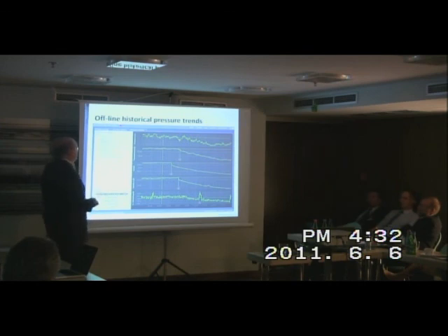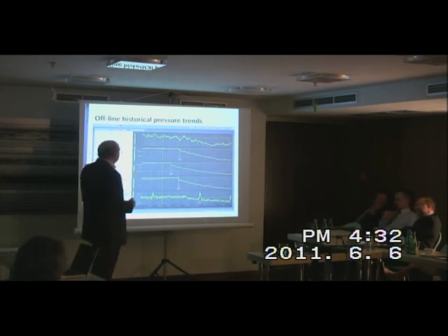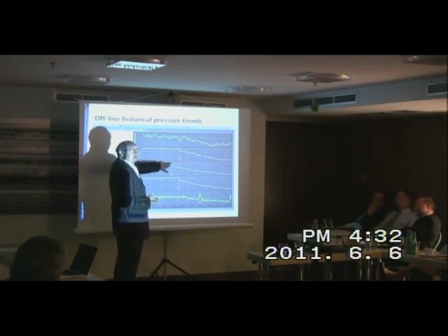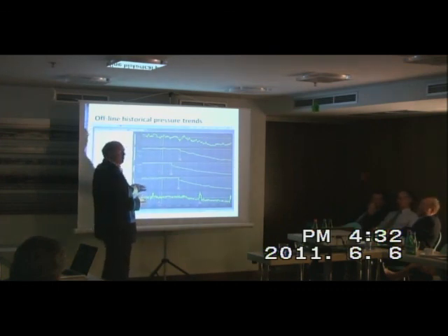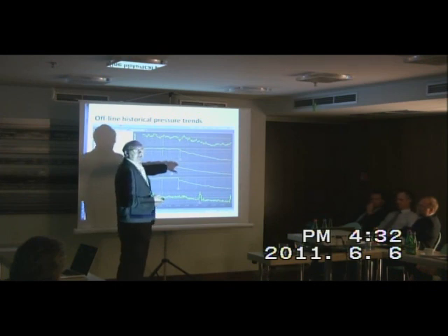The collected pressure trends are available historically; for example, here we made one for 10 minutes. Also here is an event, 5 locations. This is the pump station, this is the receiving station, and an event was produced near this blocking valve station.